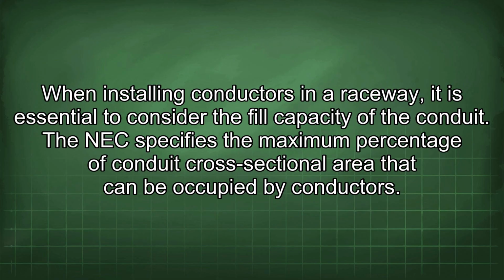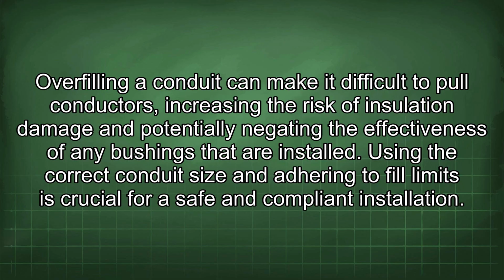When installing conductors in a raceway, it is essential to consider the fill capacity of the conduit. The NEC specifies the maximum percentage of conduit cross-sectional area that can be occupied by conductors. Overfilling a conduit can make it difficult to pull conductors, increasing the risk of insulation damage and potentially negating the effectiveness of any bushings that are installed. Using the correct conduit size and adhering to fill limits is crucial for a safe and compliant installation.